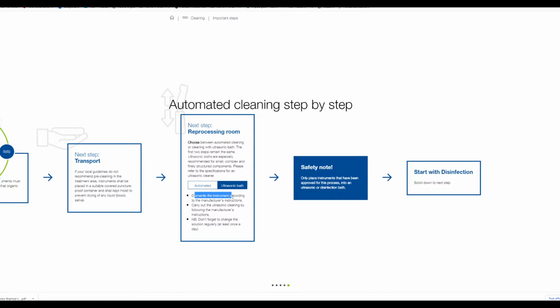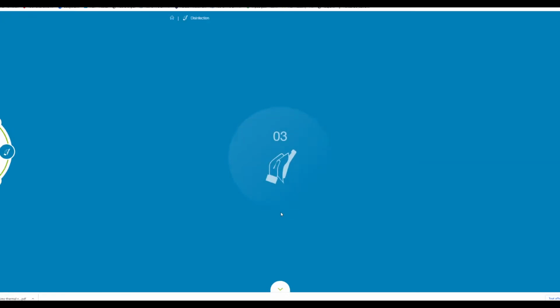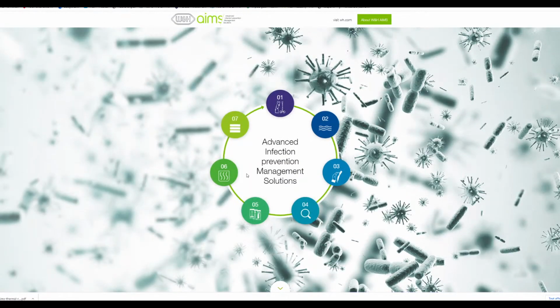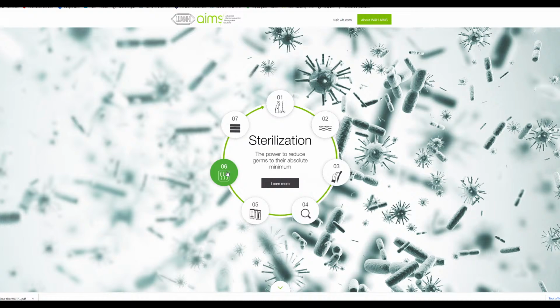It's very important also to always refer to the instructions for use, because every manufacturer has the obligation to provide you guidance on how to best use the instruments and how to use it the way the machine has been designed and checked and validated by the manufacturer. Automated, this mostly is thermal washer disinfectors, and this is our recommendation, the best choice. Then if we further scroll down, we step into disinfection. But now I want to go straight to sterilization. Learn more about sterilization.